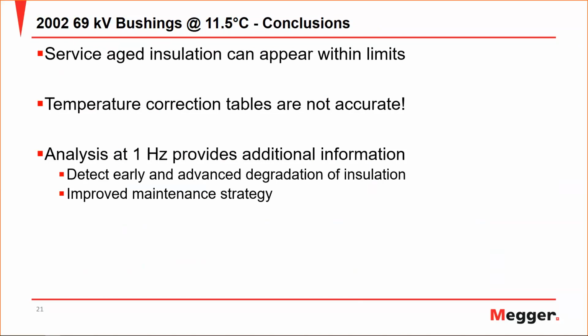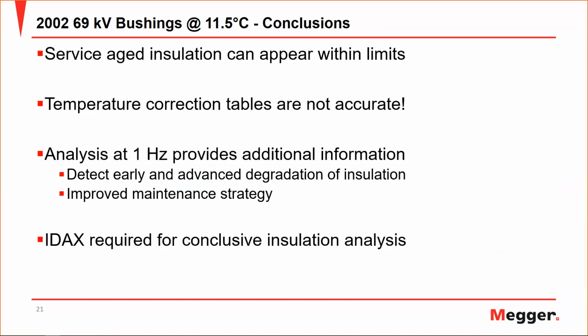Again, we're not saying to go and test IDAX on everything, although that would be my suggestion for pretty much everybody doing insulation evaluation. I would always do the IDAX because it can tell you conclusively where you are having problems. Or you could use the IDAX in this way, where you test at line frequency and at 1 Hertz to then further improve your maintenance strategy. Because at the end of the day, if you see an elevated value at 1 Hertz, you're going to have to bring out the IDAX anyways in order to get that conclusive insulation analysis.